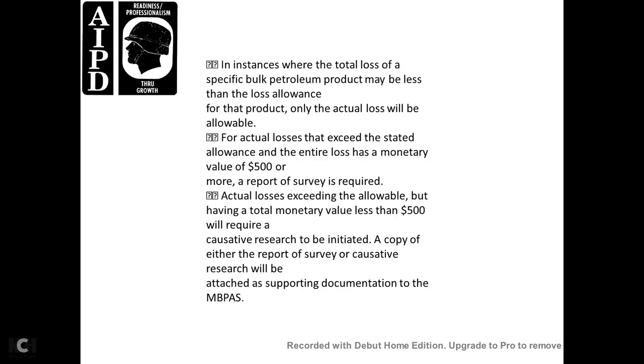Where the total loss of a specific bulk petroleum product exceeds the loss allowance — where the actual loss exceeds the allowable — the actual loss exceeding the allowance that has a monetary value of $500 or more requires a report of survey. Actual loss exceeding the allowable by a total monetary value of less than $500 will require causative research to be initiated, with a copy of either the report of survey or the causative research attached to the supporting documents of the monthly bulk petroleum accounting summary.